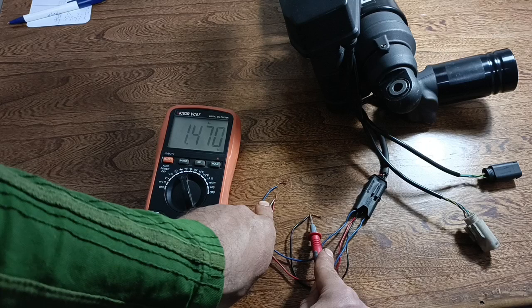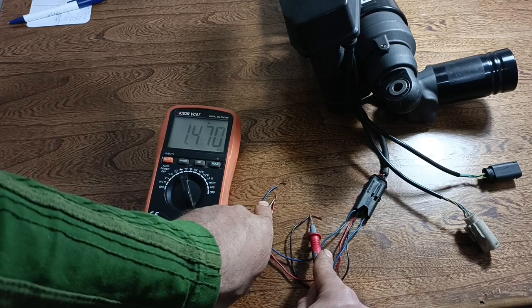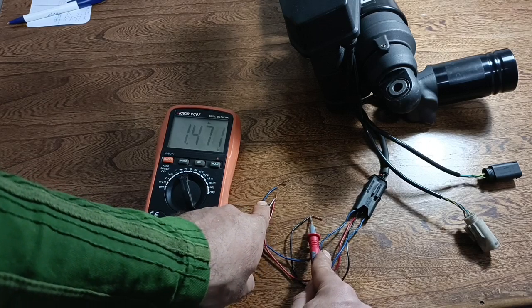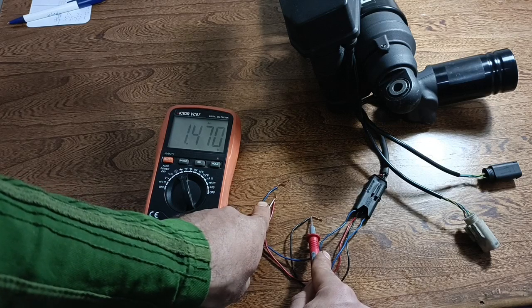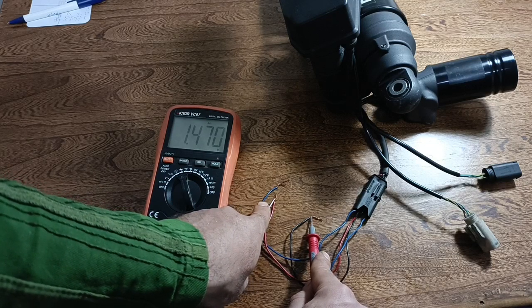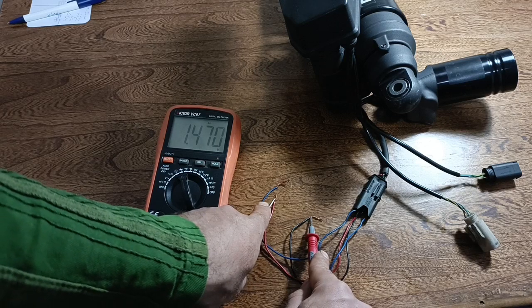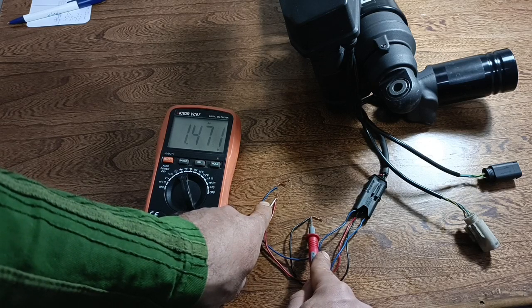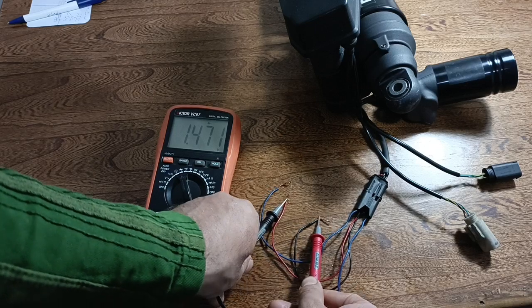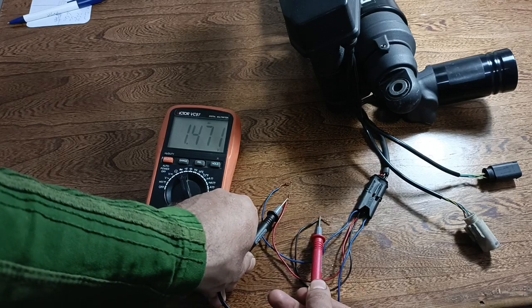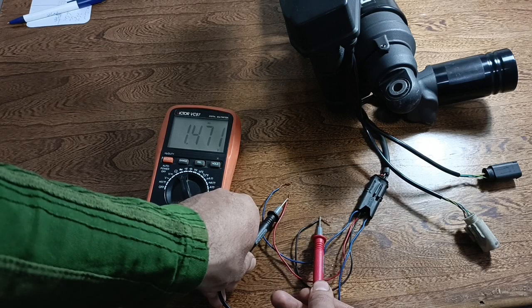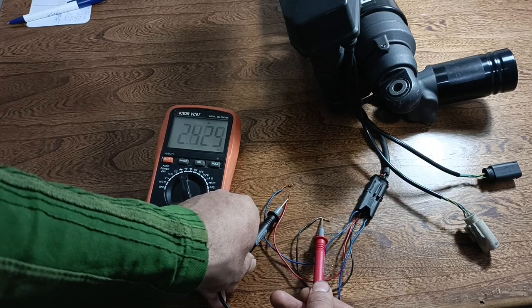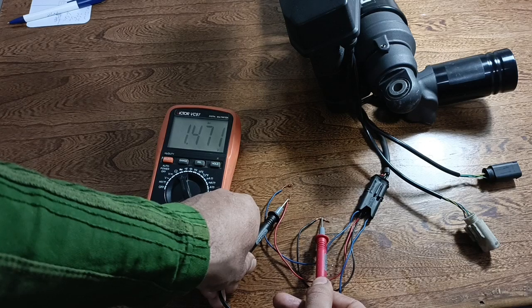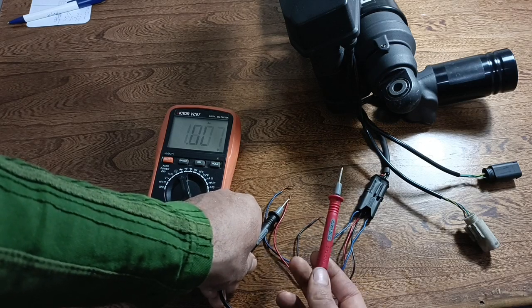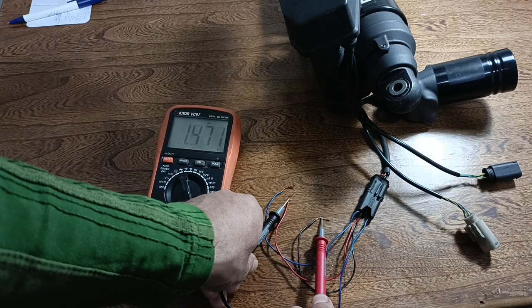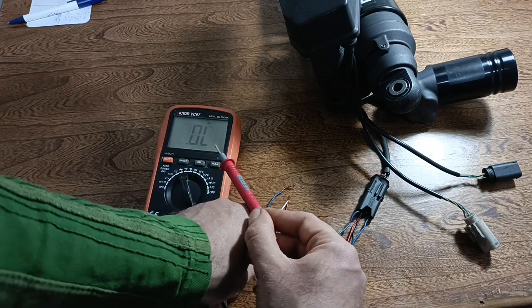We read 1.4. Remember this direction, because when we test and capture the waveforms of the Hall effect sensor in step 2, our connection will be like this: the power supply of the sensor will connect to the wire my red probe is connected to now, where I read 1.4.